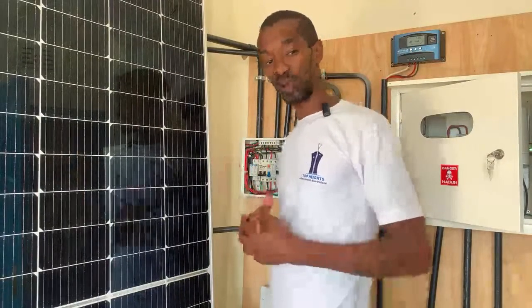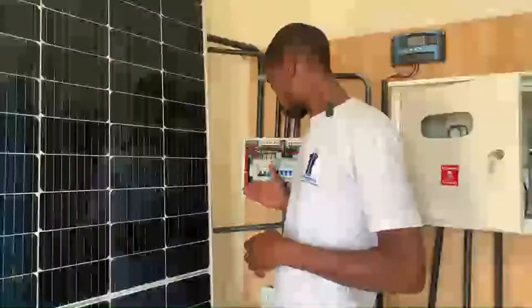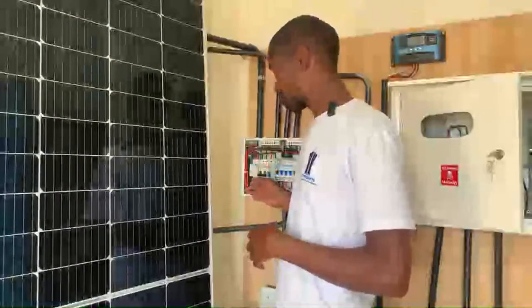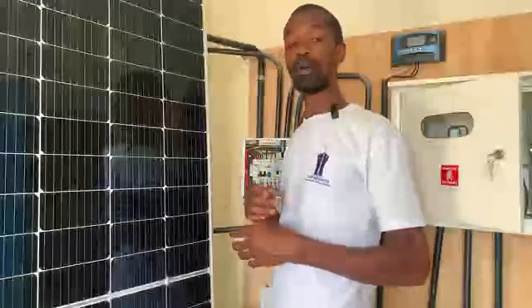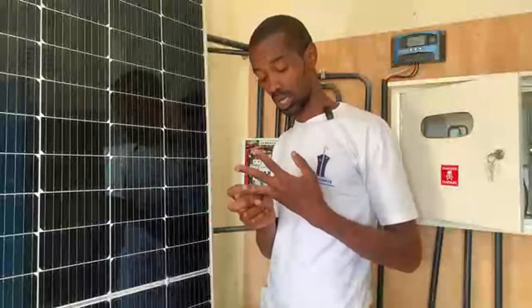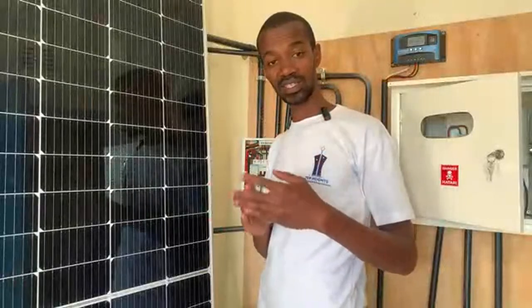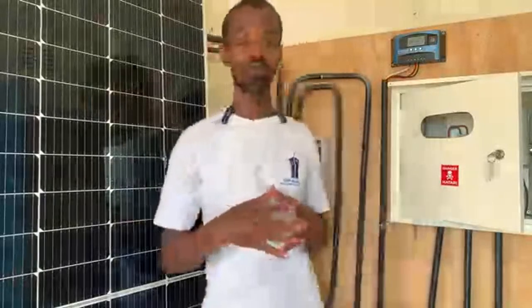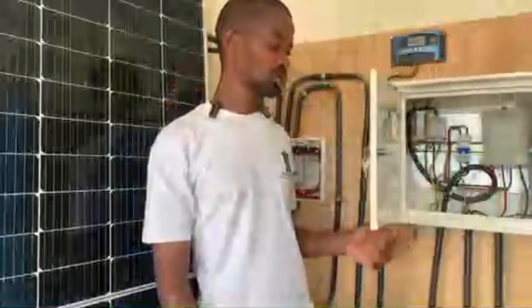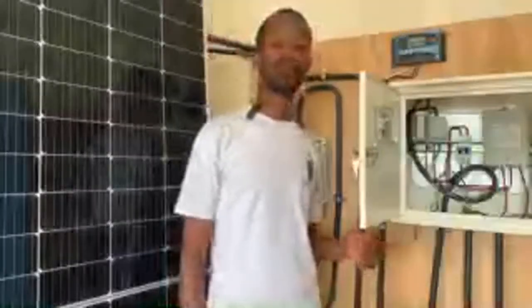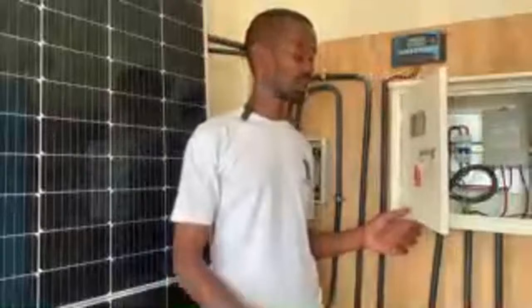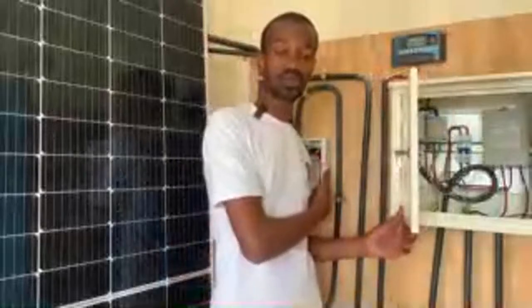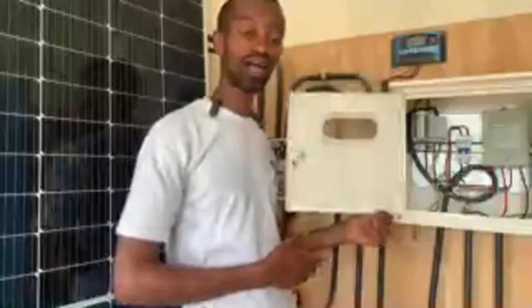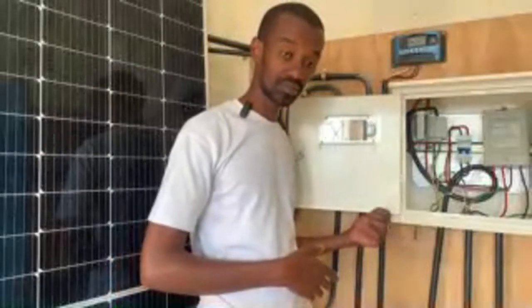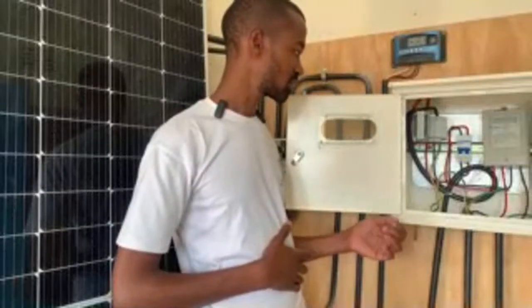We are assuming a scenario whereby all of these circuits have been connected, whereby you probably have two instant shower heads in that house, and an electric cooker in use. As an electrician, you must assume the worst case scenario, where all of these circuits have been connected. So the question is, will the mains cable connecting the meter box and the consumer unit handle that load at the worst case scenario? That is one thing you must factor in.